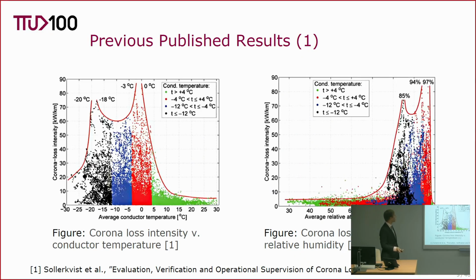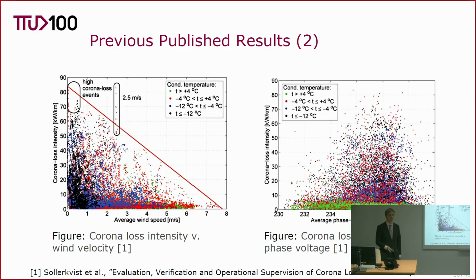To illustrate the dependence on various quantities, we can take a look at the results from a previous study carried out in Sweden with a dedicated measurement setup, including calibrated instrument transformers. We can see the dependence of corona losses on average conductor temperature and relative humidity, and also average wind velocity and phase voltage.